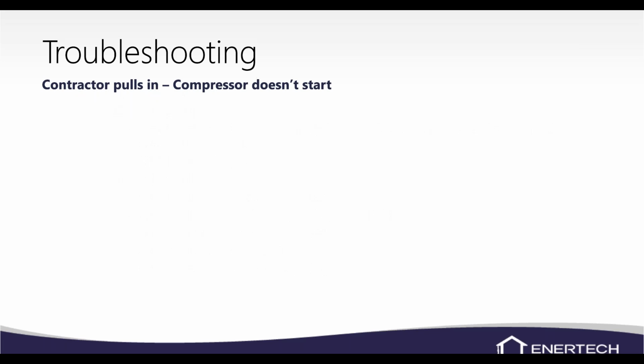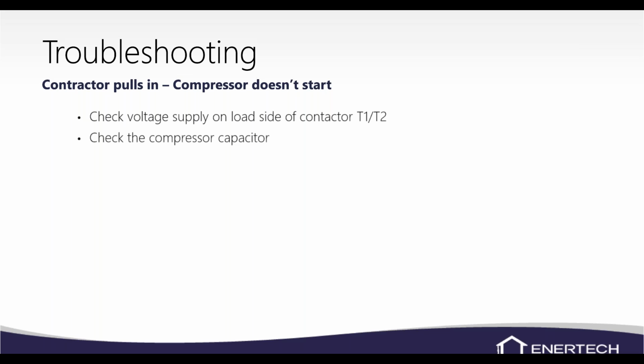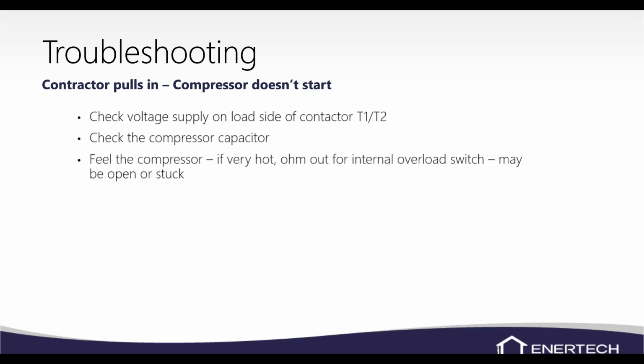If the contactor pulls in, but the compressor does not start, check the voltage supply on the load side of the contactor. So that's the T1 and T2 side. Obviously, we need our 240 volt or 208, whichever voltage you have, across that contactor. Again, check the capacitor, check the microfarad reading on that capacitor. It needs to be, normally I think, within about 5% of what it's rated for. So make sure that the capacitor is operational.